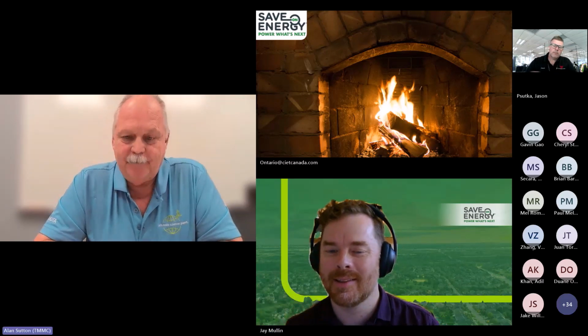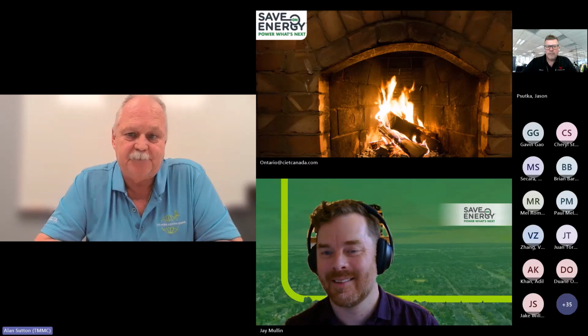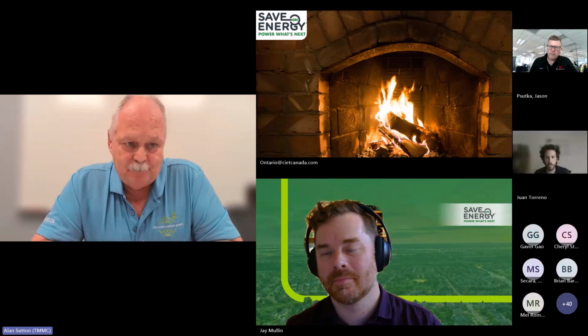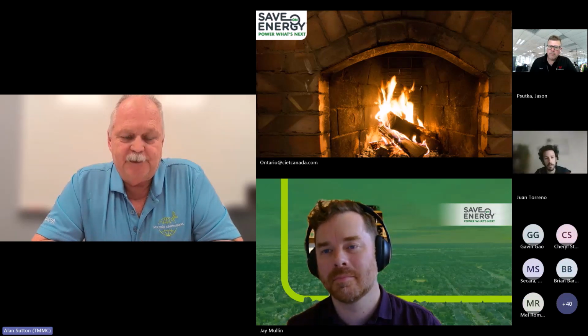I'm going to be fully transparent. When we first did the audit, it was visual in nature. We saw the VFDs and said, check, yep, we got it, move on. But when we went into the second phase of the energy audit, where we started looking at timing and comparing control setting changes to outcomes, we found that we could change the settings and it had zero impact on the outcome. That's how we discovered it.